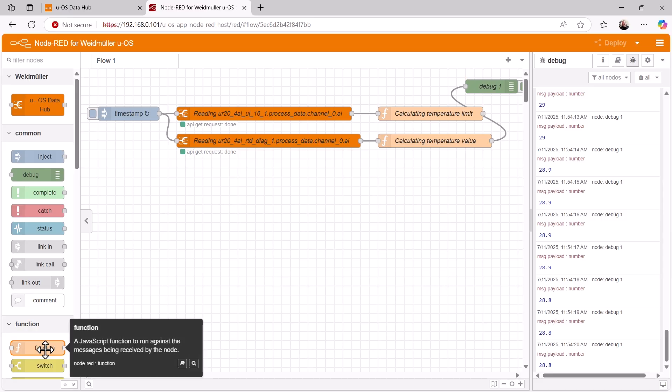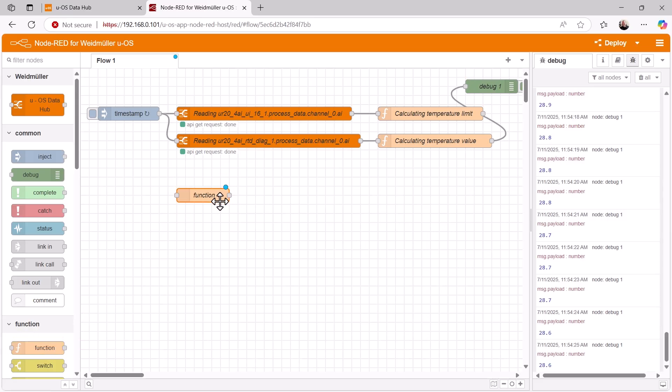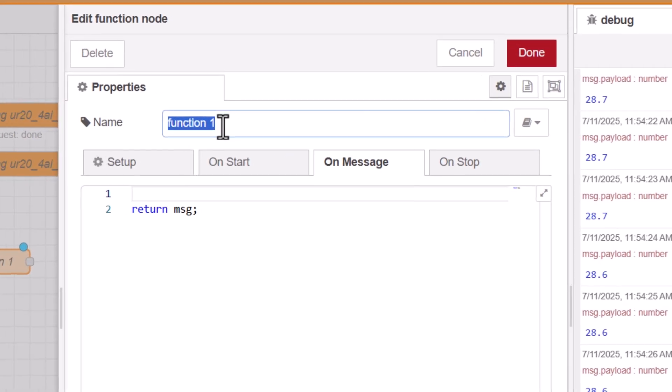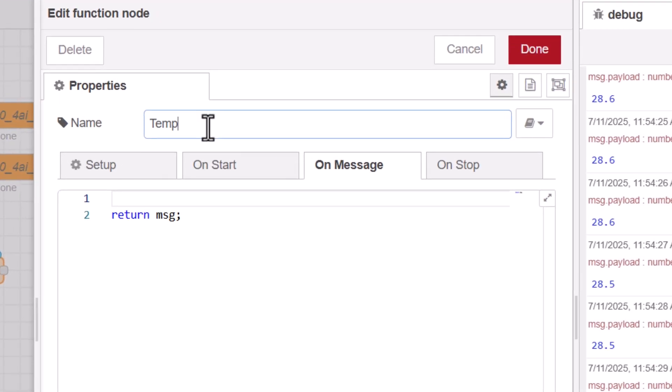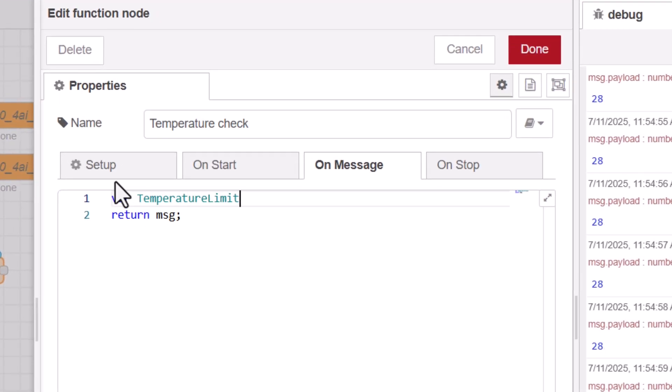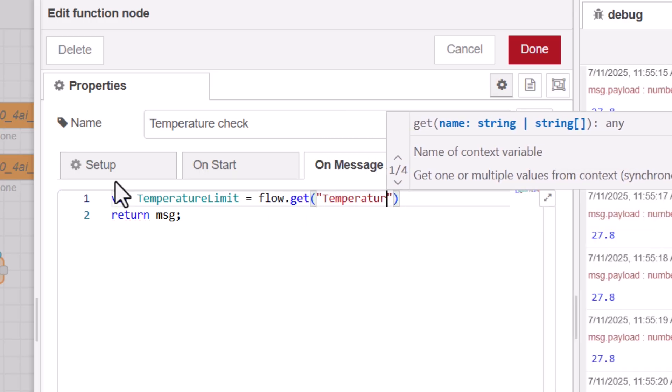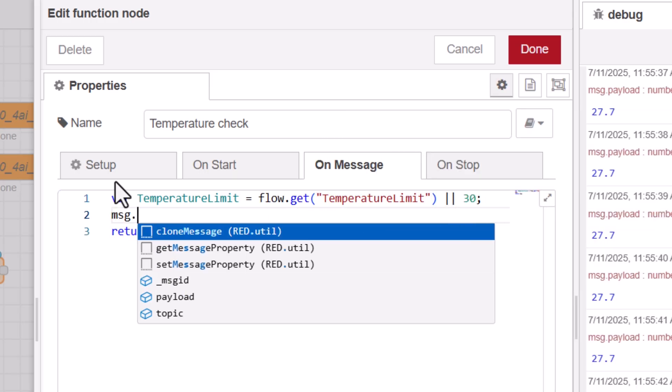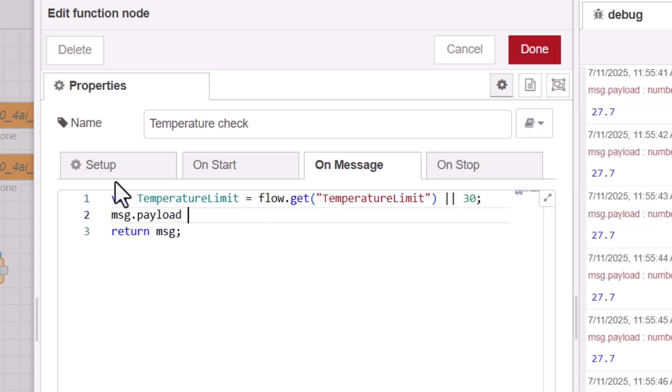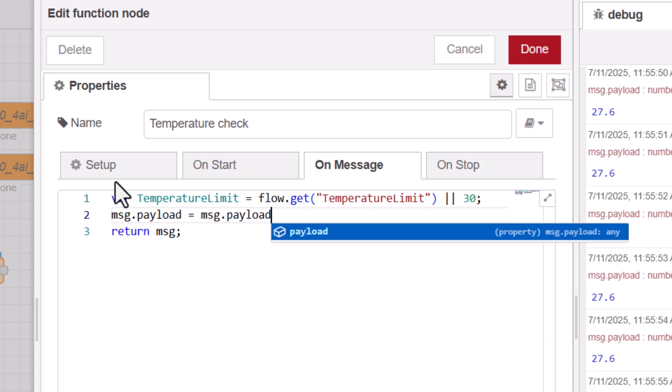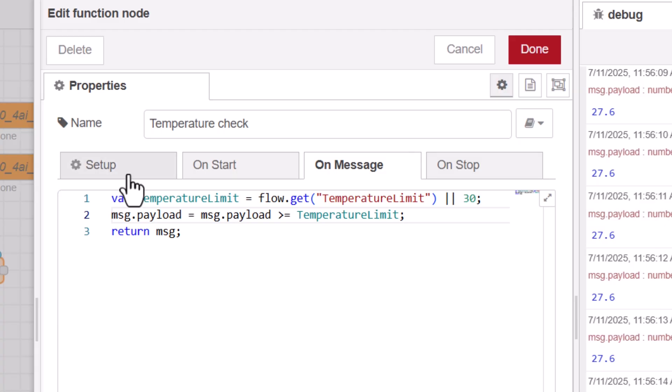Next, we will check whether the temperature value has reached or exceeded the limit value. To do this, we write another function and give it the name temperature check. First, we retrieve the stored temperature limit value. In the next step, we compare the input value of the node, that means the temperature value, with this limit value. The output of this function node is a boolean value that is set to true if the temperature reaches or exceeds the limit value.